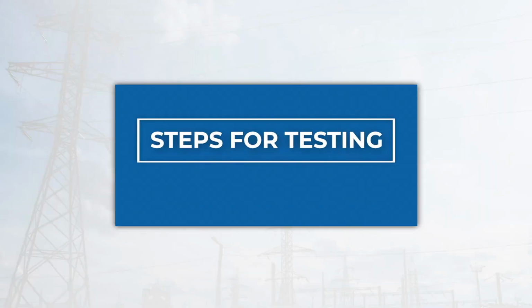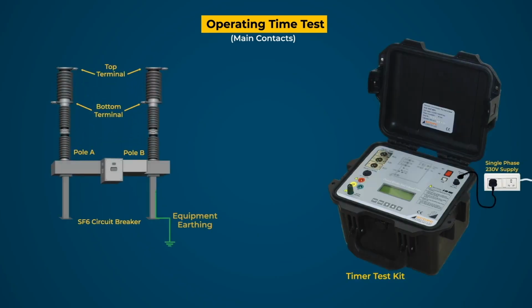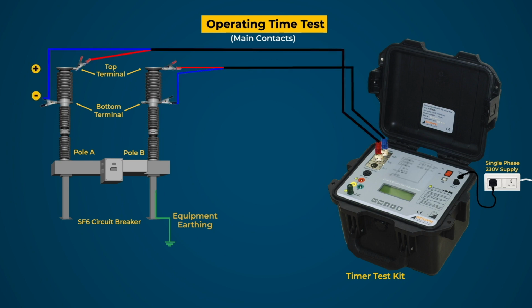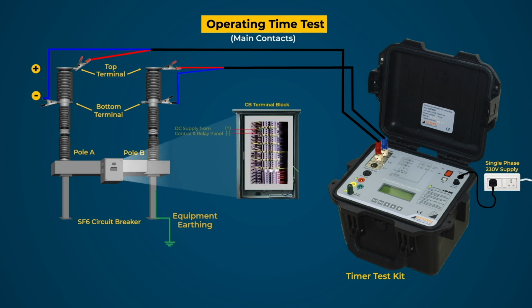Steps for testing. First, open the connections of both end terminal connectors. Connect the contact timer lead of the tester to the top terminal and bottom terminal of both the poles of the breaker. Now connect the breaker controls lead of the tester to the terminal block of the breaker one by one at the DC point, close coil terminal, and trip coil terminal.